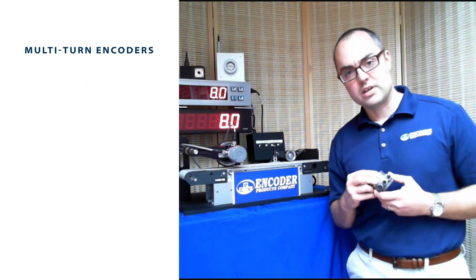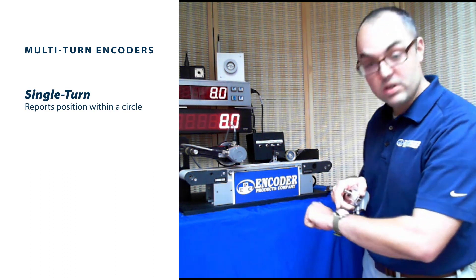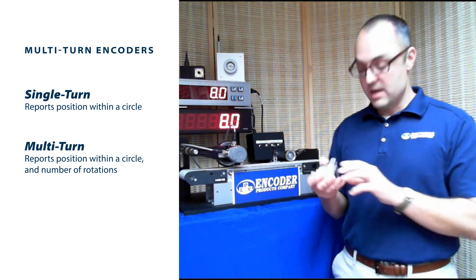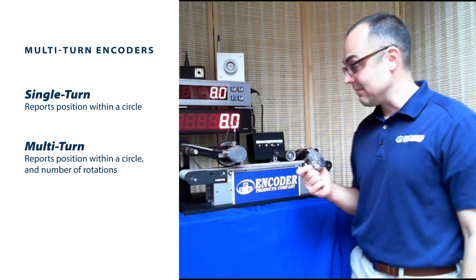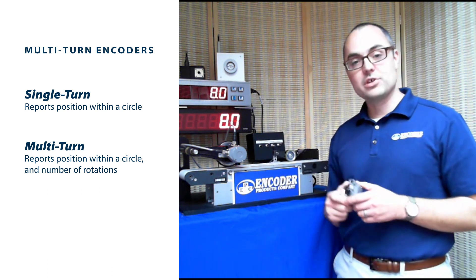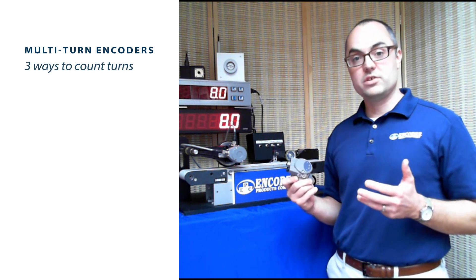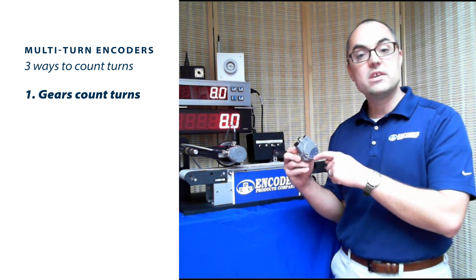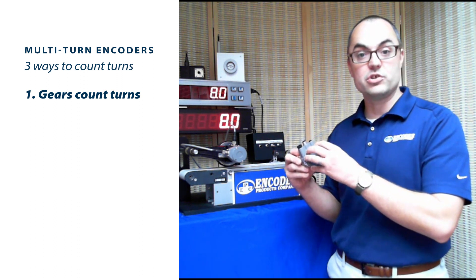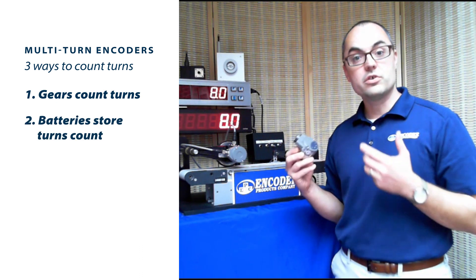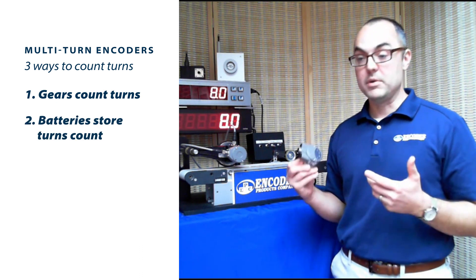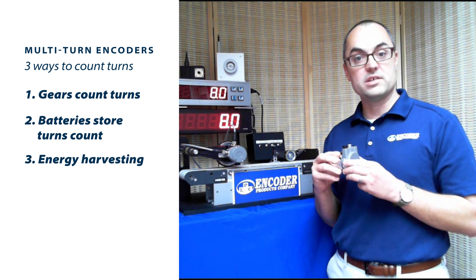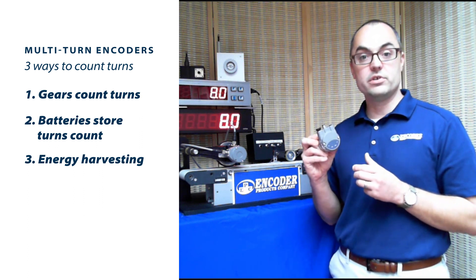An absolute encoder will give you the position within a circle, but it'll also give you the number of rotations if you select a multi-turn encoder. Multi-turn encoders are pretty special — counting turns is counting turns, but how it's accomplished is very important. There are three main ways: using gears, a battery backup system to store the count in memory, or the newest way — energy harvesting — which is what our multi-turn encoders use.